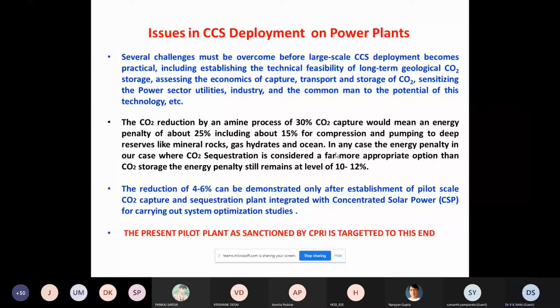So reduction cannot be allowed more than 4 to 5 or 6%, and that is not possible by taking steam from the boiler. If you take steam from the boiler, minimum penalty will be 13%, 15%, 20%. It's a very high penalty, and this penalty will increase the cost of generation of a thermal power plant.